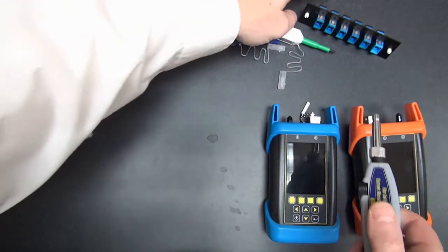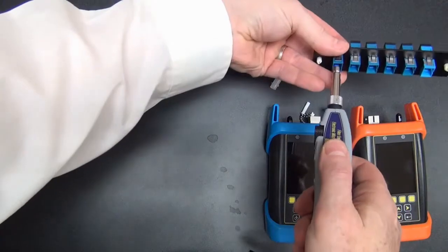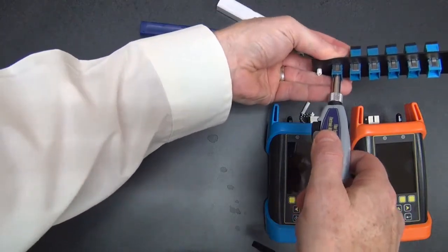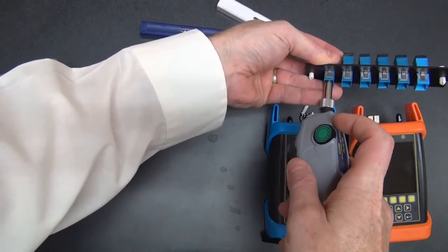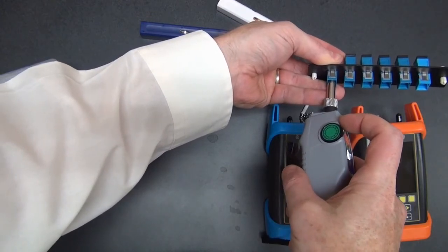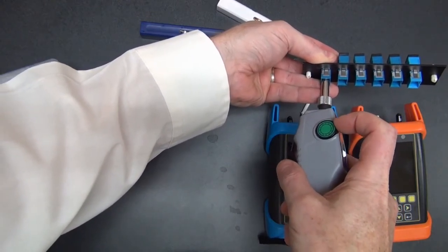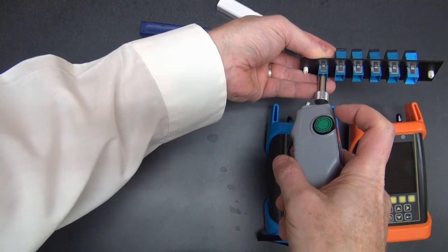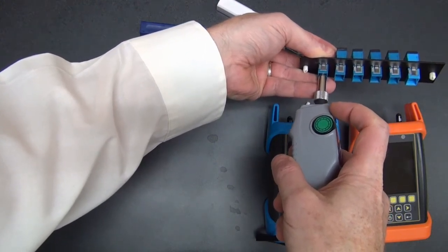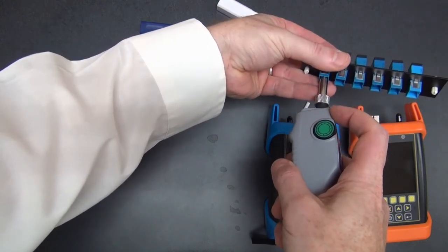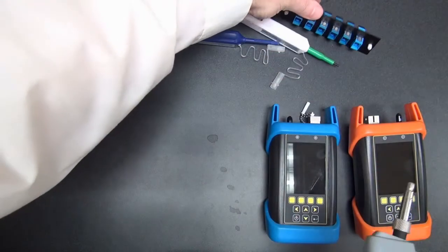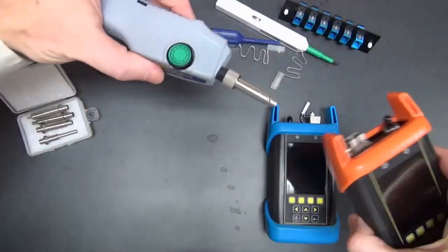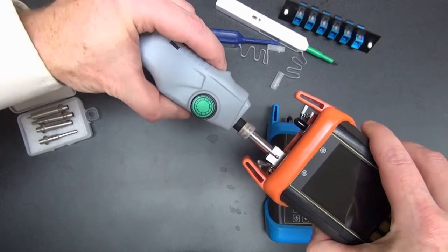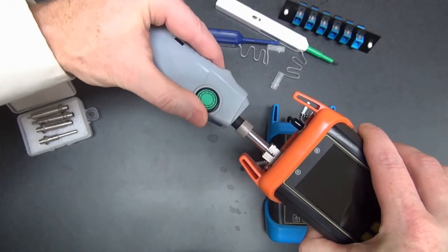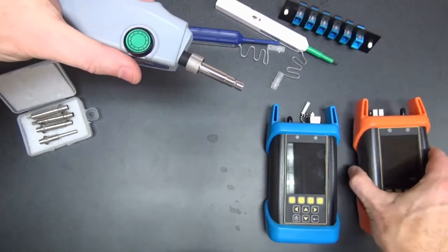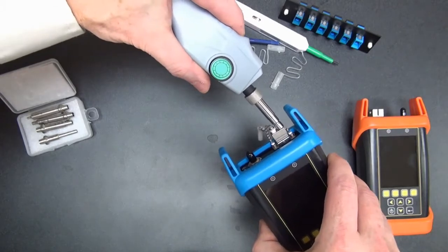So here's how this works with a patch panel. You simply plug into the patch panel. You will wait for the end face image to appear on the screen, and then you can use the focus wheel to focus. The nice thing about probe microscopes is that you can also capture the end face images for later analysis. Likewise, we can use the 2.5 millimeter tip here for SC. We can clean inside our light source. However, this won't work with LC.